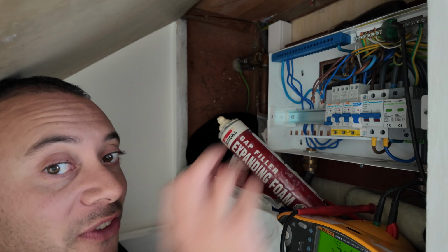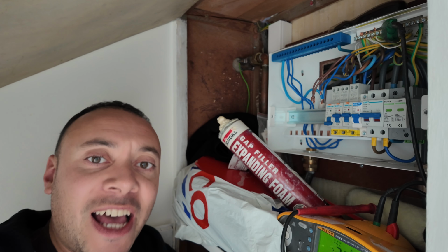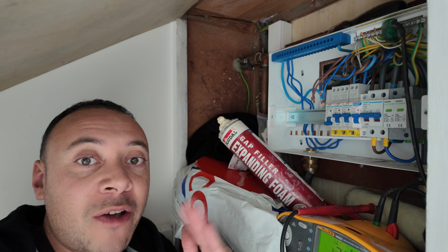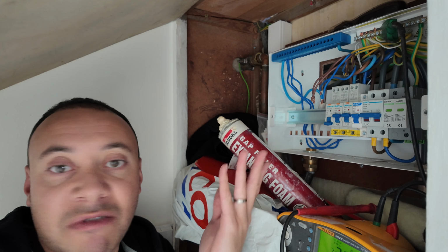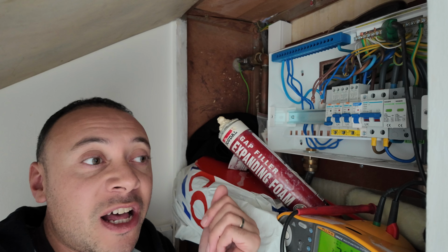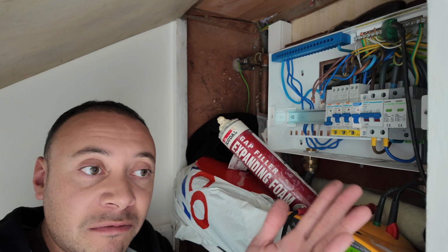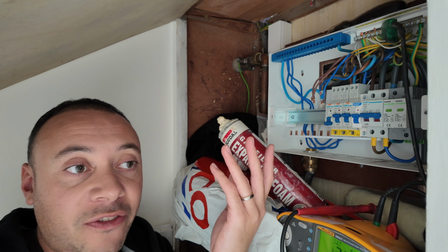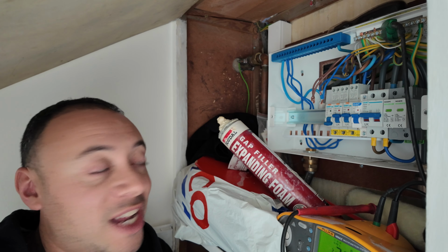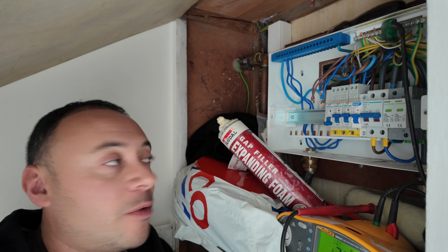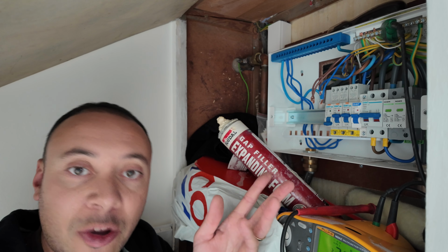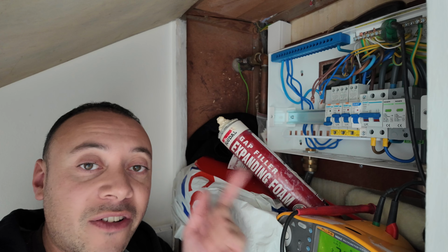Unless you have an intermittent fault, sorry, I got this on my head. Unless you have an intermittent fault, you can have a fault that comes and goes depending on its situation. Say it's water ingress, for example, then you can get a fault, but give it a day or two and it can go because it will dry out if water's got in. So you've got to be a little bit careful when you're looking for these things. Just because it's showing clear now, it doesn't mean it will in a day or two, but we can only work with our current scenario.